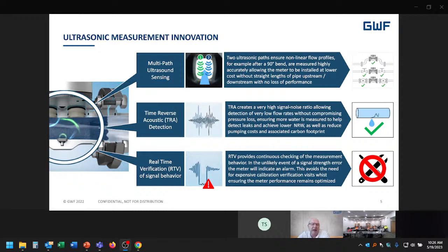And as well, if we're looking at that DNA, that fingerprint, we're able to look for verification of signal behavior. So if there's an issue, we can see that change and we can raise an alarm. So these products are getting more and more intelligent. We're able to avoid the need for expensive calibration and field verification visits by looking at that DNA, that fingerprint, automatically. So that's something on time reverse acoustics. Very good for measurement of flow, final effluent, raw water applications, clean water applications. If it's wastewater, then MagFlow can still be good, but we're going to look at an alternative technology in a short while.